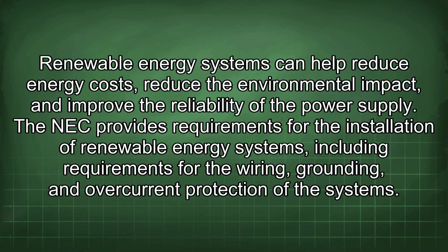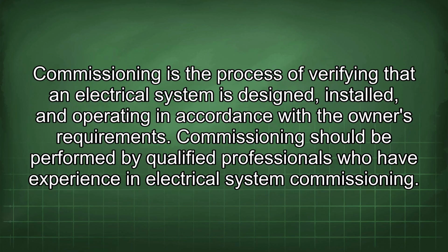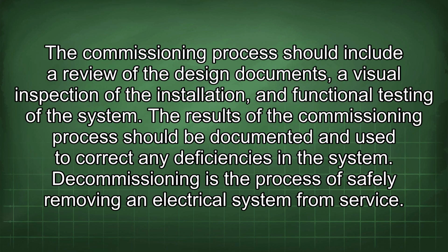Commissioning is the process of verifying that an electrical system is designed, installed, and operating in accordance with the owner's requirements. Commissioning should be performed by qualified professionals who have experience in electrical system commissioning. The commissioning process should include a review of the design documents, a visual inspection of the installation, and functional testing of the system. The results of the commissioning process should be documented and used to correct any deficiencies in the system.